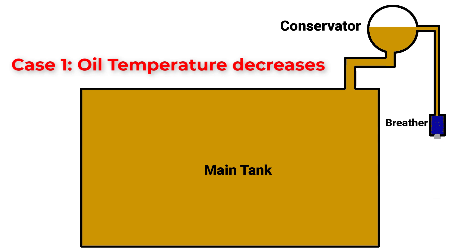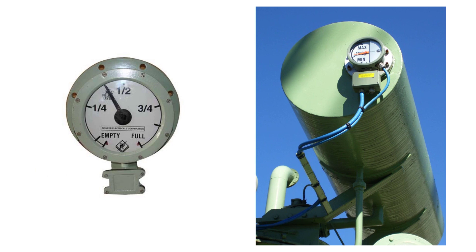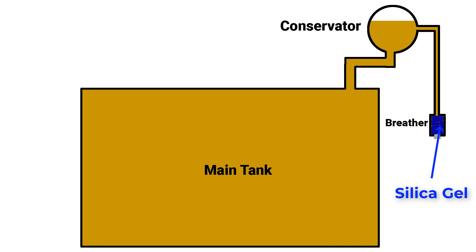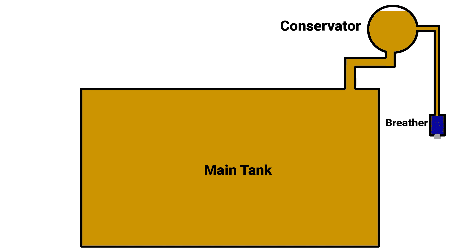The rest of the space inside the conservator is occupied by air volume. When oil temperature decreases, a contraction in oil will happen which causes more inlet air through the breather to compensate the contracted volume. When oil temperature increases, oil expands and pushes the extra air outside the transformer through the breather. This process of air in and out through the breather is called transformer breathing. On the conservator there is a level gauge to show the level of oil. Silica gel is found inside the breather to prevent moisture from the inlet air, and an oil cup is connected to catch any contaminations in the air.